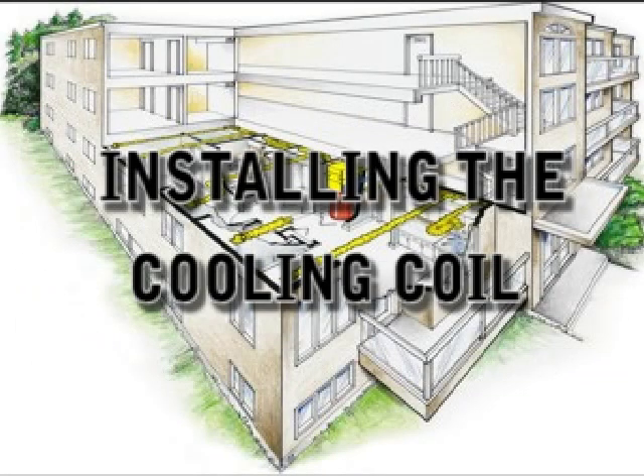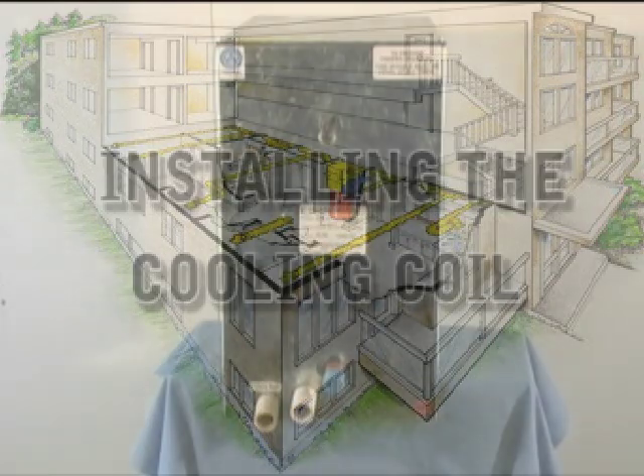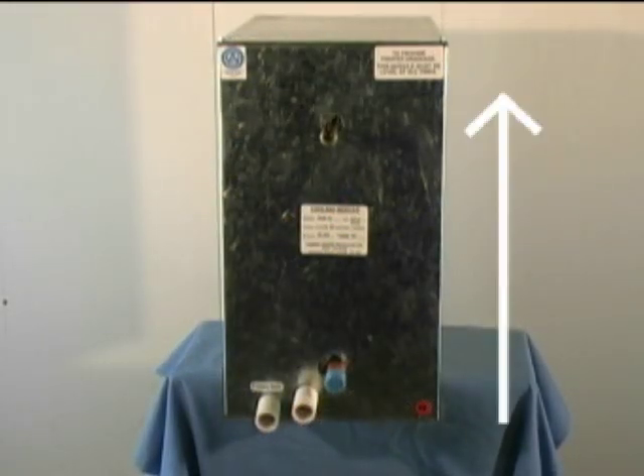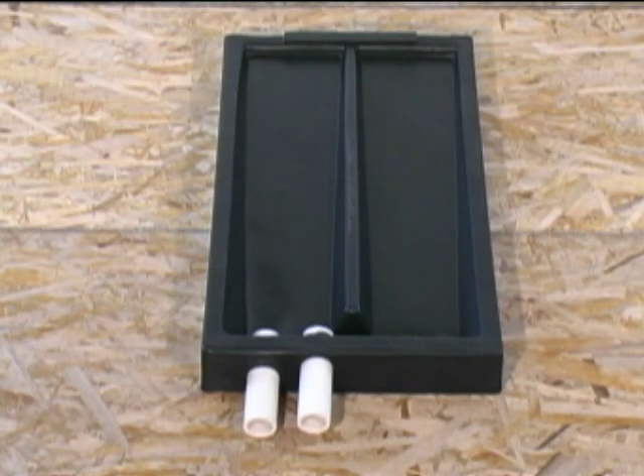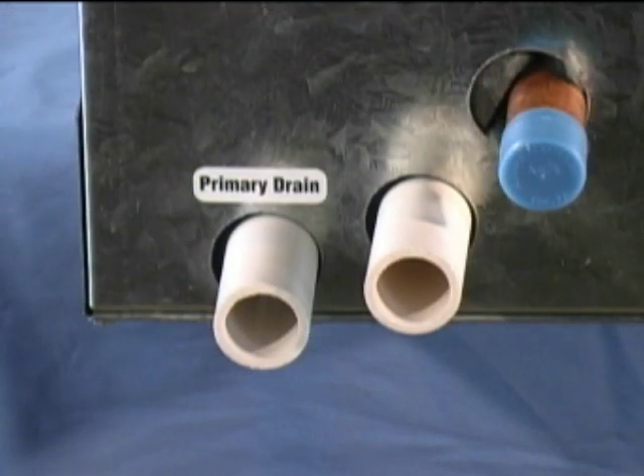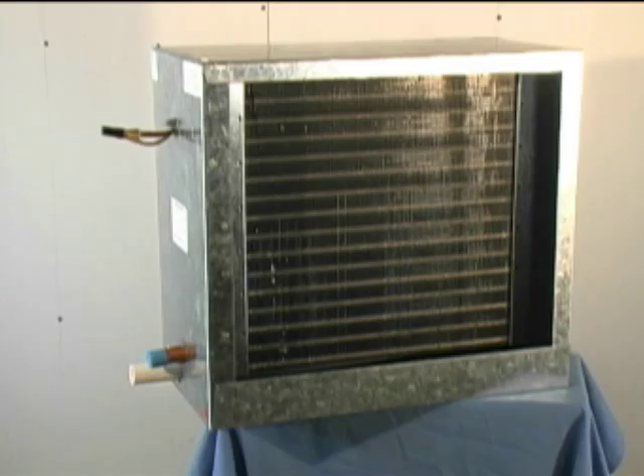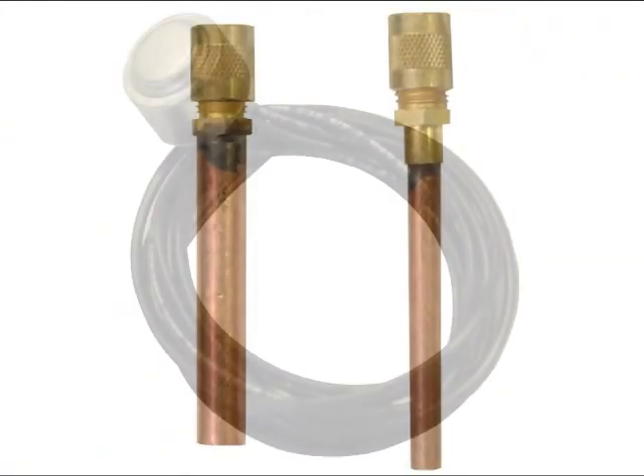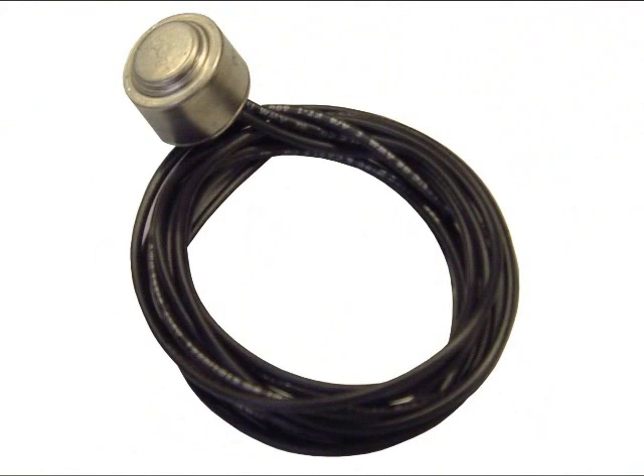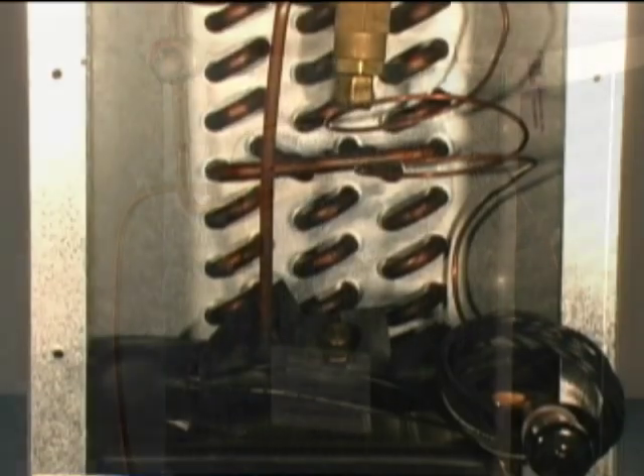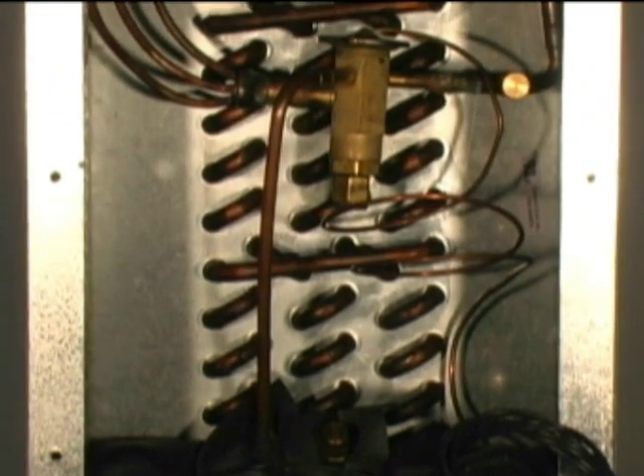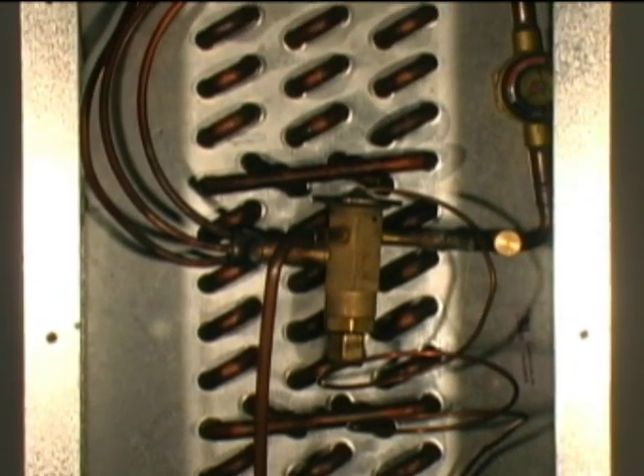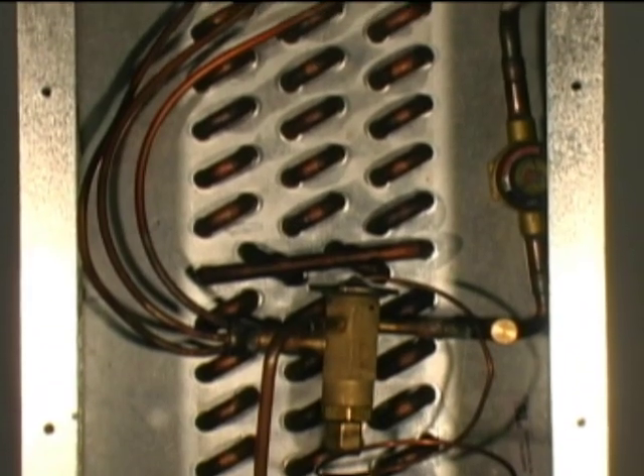Installing the cooling coil. When installing a high-velocity system's cooling modules, they must always be installed in the vertical position. This will allow the positive flow drain pan located inside the cooling module to properly drain condensate. The refrigerant cooling module (RCM) comes complete with R22 thermal expansion valve, sight glass, two access ports, and an external freeze stat to be installed at the fan coil. With the refrigerant pre-pipe modules (RPM), the expansion valve, sight glass, access ports, and freeze stat are factory installed.